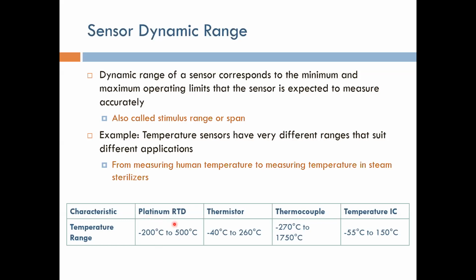For example, a platinum RTD has a dynamic range from minus 200 to 500 degrees centigrade. A thermistor is minus 40 to 260. A thermocouple is from minus 270 to 1750, at least for one type of thermocouple. A temperature integrated circuit is from minus 55 to 150.